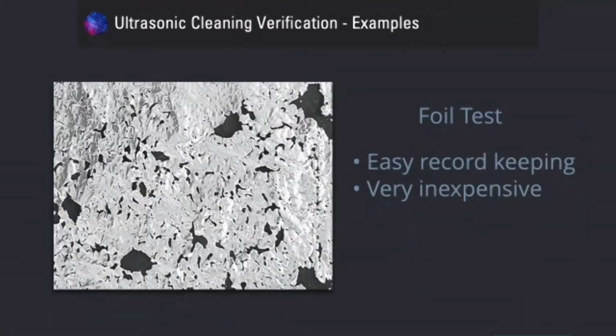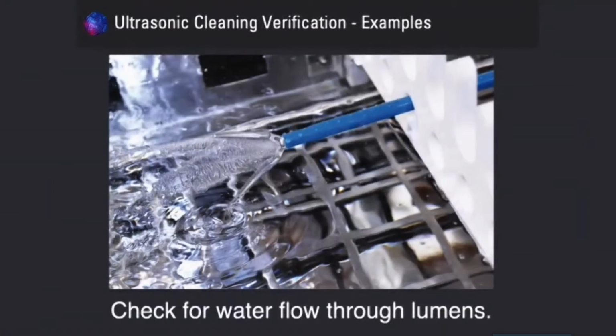So here's a foil test that's been tried and true. You've heard it probably many times, and it is great for easy record keeping and very inexpensive. This is showing the pitting that occurs when you have these foil strips inside your basin and the sonication is effective. And also, of course, again, check water flow through your lumens, check your lumens.